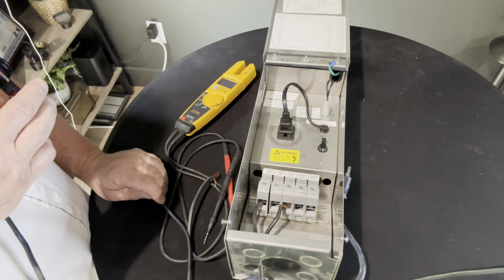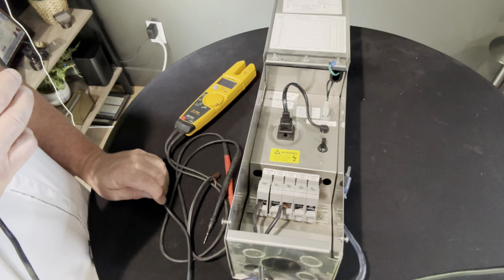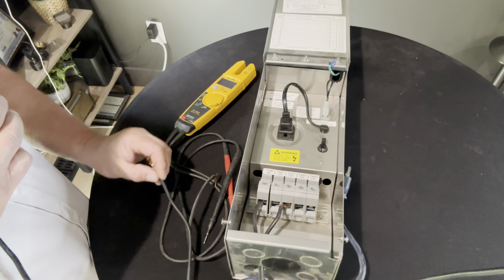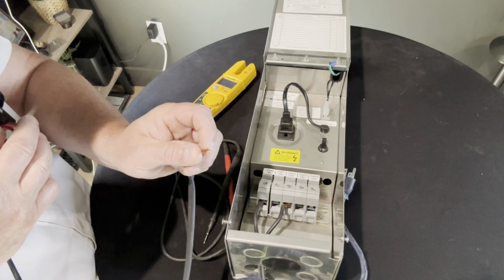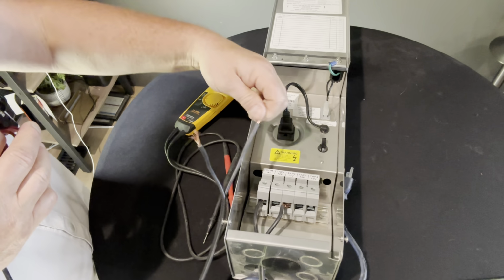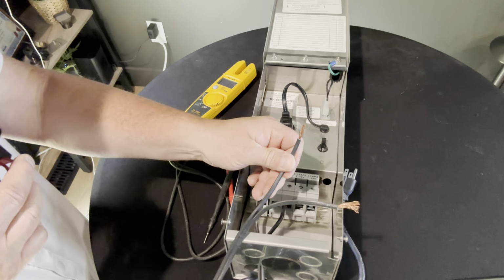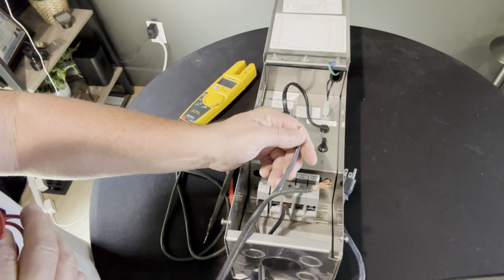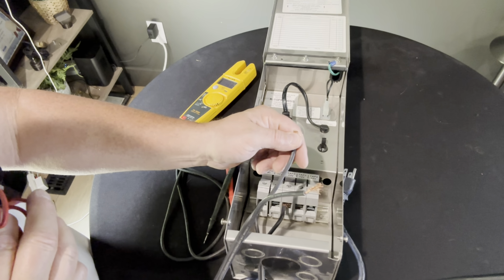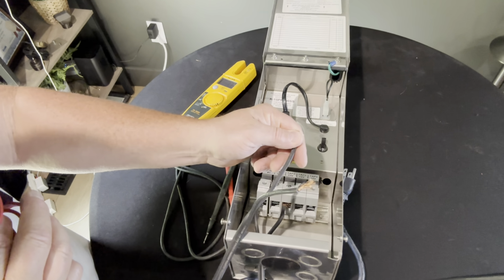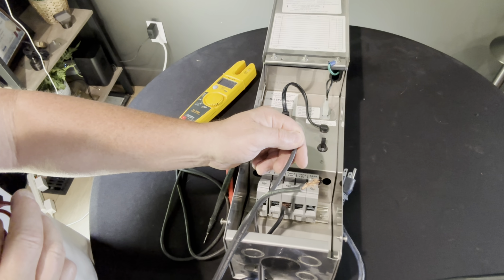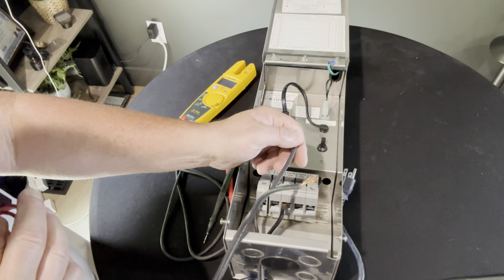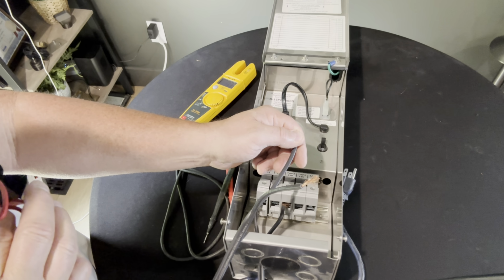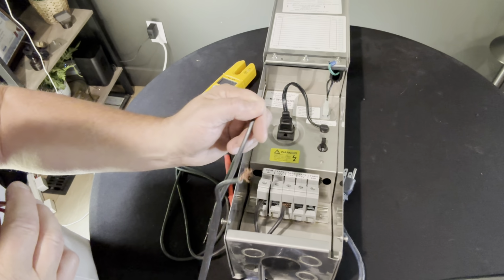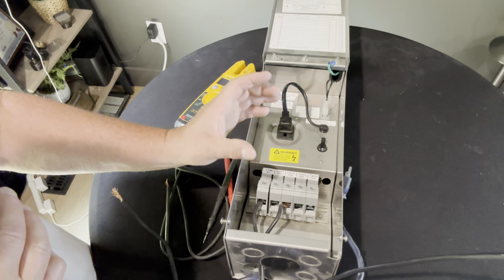And if you wanted to see how much voltage you have at a particular area in the system, you would want to have these exposed. Even if you've got your lights hooked up to it, that's actually better. That way you get a true reading because it's got the load on it. The system has to obviously be on, and then you can see what your voltage is. Your operating voltage for most fixtures, if you are doing a field test, is going to be between that 9 to 15 volts, depending on the manufacturers. Some of them say 10, some of them say 9, but they're typically between that 9 to 15 volts is how much power the fixture needs to operate correctly.